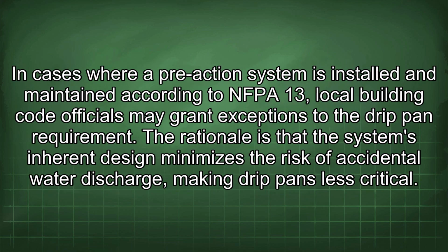In cases where a pre-action system is installed and maintained according to NFPA 13, local building code officials may grant exceptions to the drip pan requirement. The rationale is that the system's inherent design minimizes the risk of accidental water discharge, making drip pans less critical.